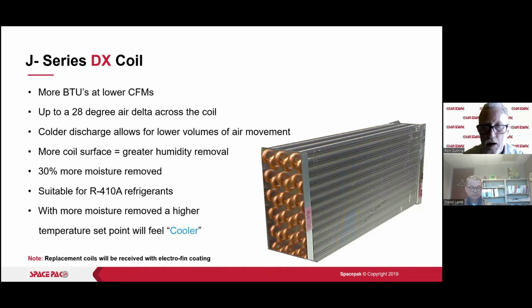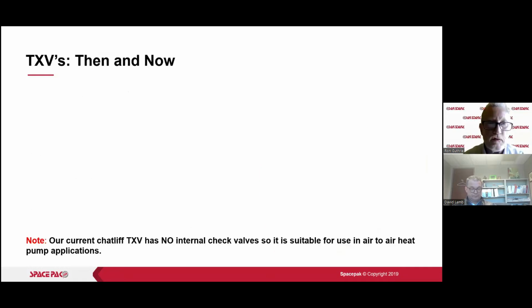This is an inherent efficiency that does show in the SEER rating as well. All right, more moisture removed. Theoretically, the customer would feel more comfortable at a higher temperature, because there's a lower dew point in the room or the area in the house or the building. Dew point is really the factor that makes us feel uncomfortable, how much humidity is in the air. So inherently they should feel more comfortable.